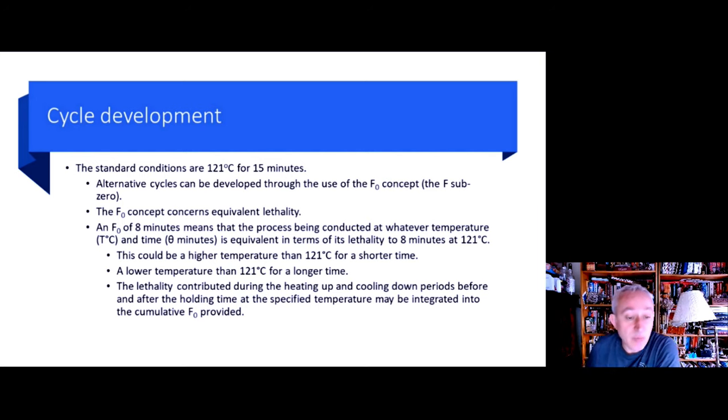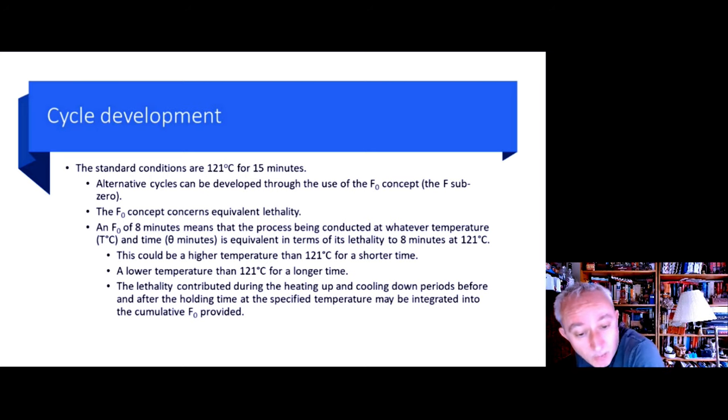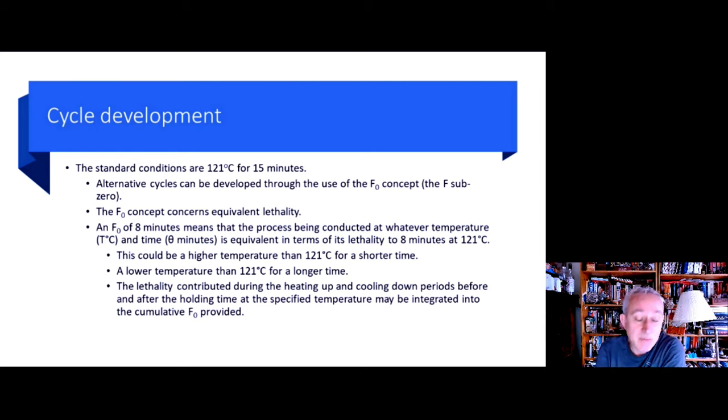So, an F sub zero of 8 minutes means that a process being conducted at whatever temperature and whatever time is equivalent in terms of lethality to 8 minutes at 121 degrees Celsius. This could be a higher temperature than 121 degrees Celsius for a shorter time, or a lower temperature than 121 degrees for a longer time. For example, if we want to run an autoclave at 110 degrees Celsius, because that is optimal for sterilizing microbiological culture media, because it's damaged at a higher temperature, we would need to know how long to run that autoclave for. So, if it takes us 12 minutes to sterilize at 121 degrees Celsius, then the F sub zero concept will tell us how long we need to run the autoclave at 110 degrees for. And that might be 20 minutes, for example.